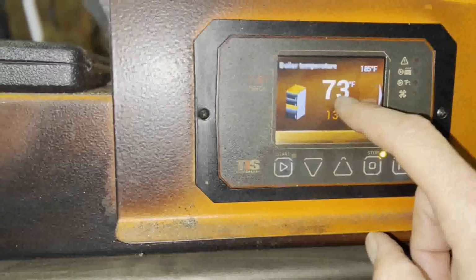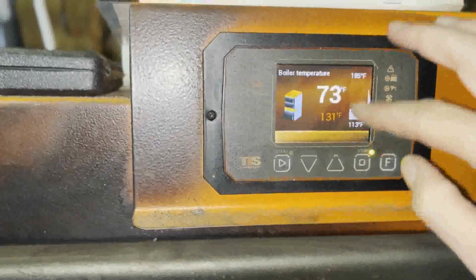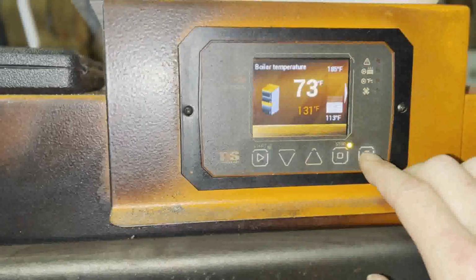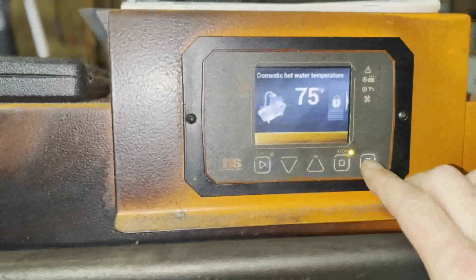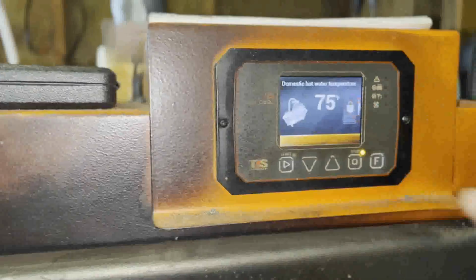Yeah, it has some passages here where water is moving around to help capitalize on heat exchange surface area. Down here, that would be your clean out. Okay. So the controls of the boiler itself, obviously you have your temperature of the water, the set point. These are your min maxes. This is set up to integrate right to a domestic water storage.